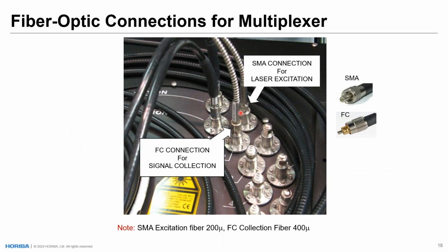Here is a zoomed in image of our multiplexer with two different fiber optic cables interfaced into it. The top one here is an SMA connection for laser excitation. This is what brings the laser light to your sampling point. And the bottom one here is an FC connector, shown in these images on the right. This is what brings the Raman signal back into the multiplexer, which then gets brought into the spectrograph.